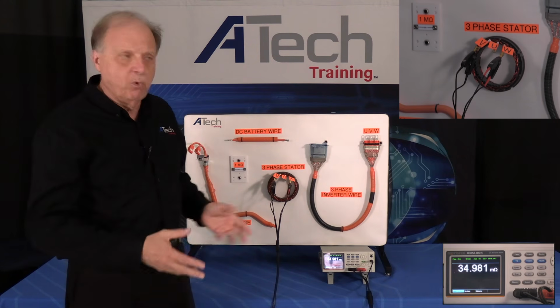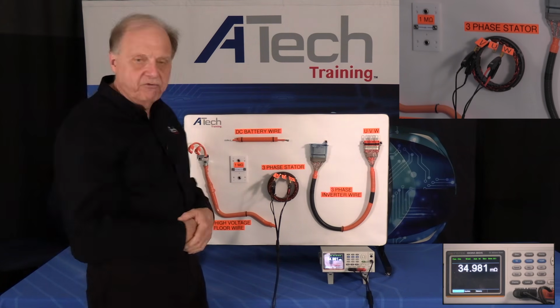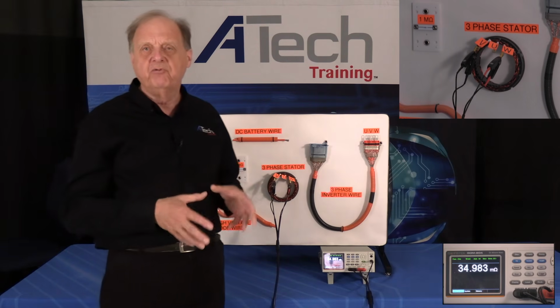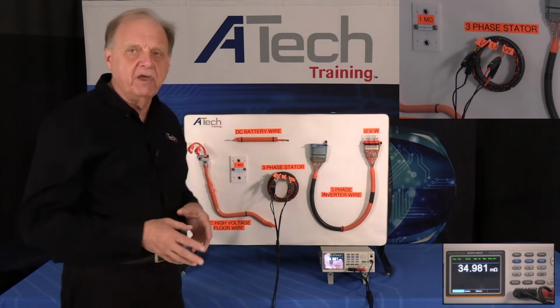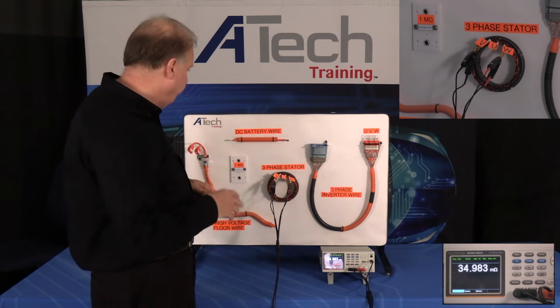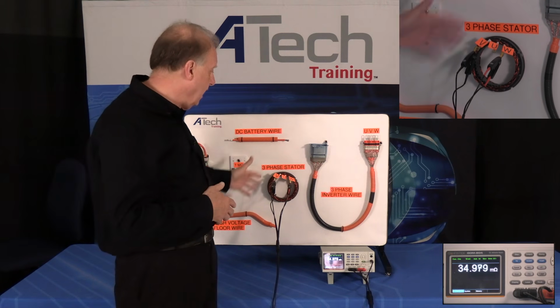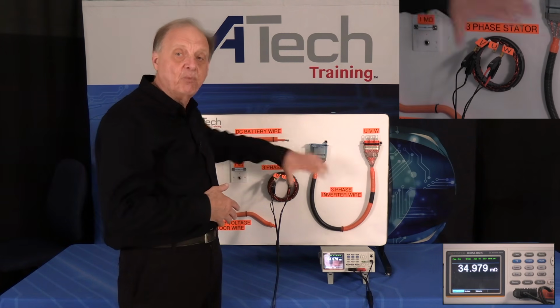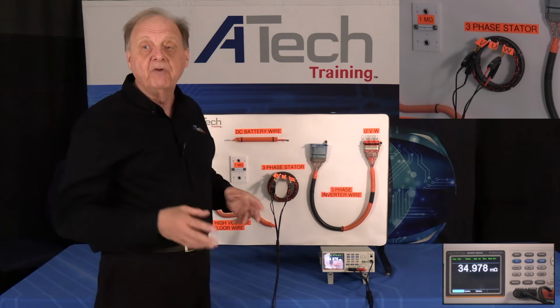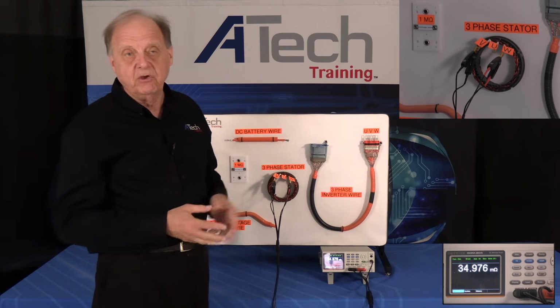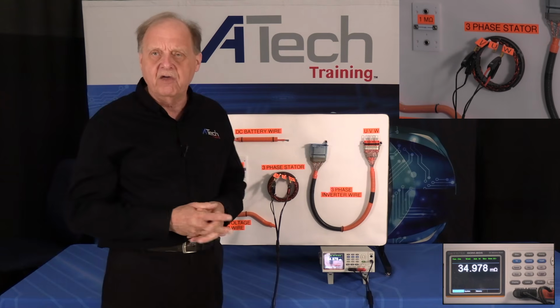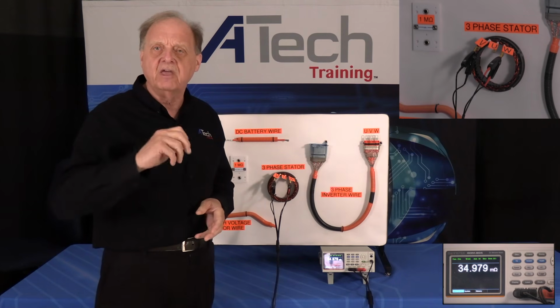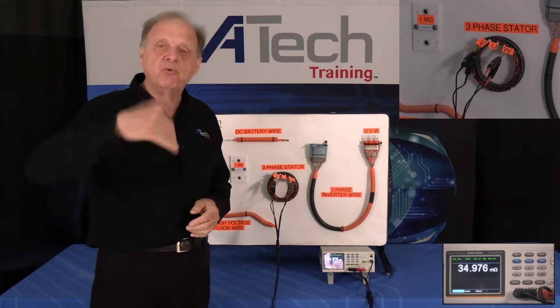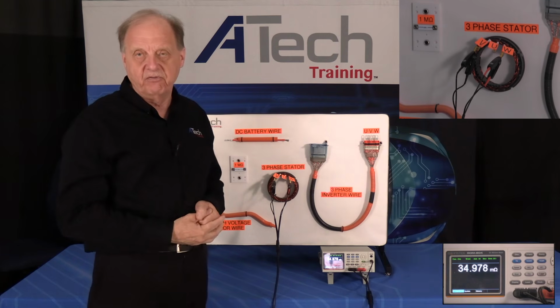This works real good, but if you're out doing this testing, these meters are very temperature sensitive, so make sure you account for temperature correction. If the temperature changes, it will cause the readings to shift. One thing you can do when showing your guys how this works is take canned air and spray it on the meter, and you'll see the readings change because of the temperature.